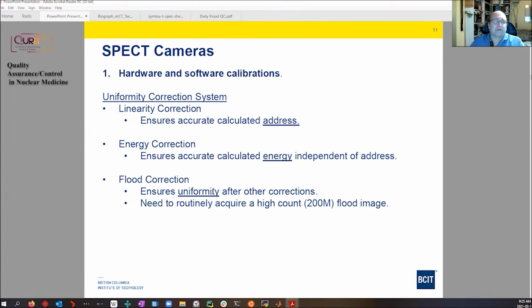So again, going back, what do we do? First, we worry about calibrations. One of the more important calibrations is called the uniformity correction system. It has three parts. The first part is called the linearity correction, where the inaccurate addresses, which were caused by this non-uniform light sampling, are corrected. The non-uniform light sampling also causes the calculated energy of the gamma ray to be dependent on where the gamma ray hits. So if the gamma ray hits over the center of a PMT, the calculated energy is slightly too high.